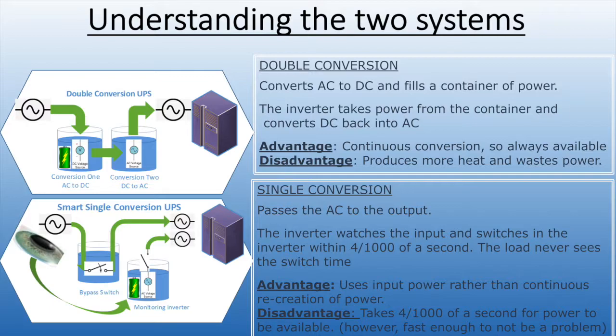Now, you might say, well, then the upper one is more desirable, but the upper one is actually using energy all the time. This double conversion is heating things up, and you have a much higher chance of failure, not to mention it's not that efficient. The lower one, because the electronics is so fast, it can actually switch out the grid and switch in the battery before the load even sees it. This is the way smarter UPSs are working. Its advantage is that it's much more efficient and it wastes much less energy, and it's fast enough that the load just doesn't see the switch.